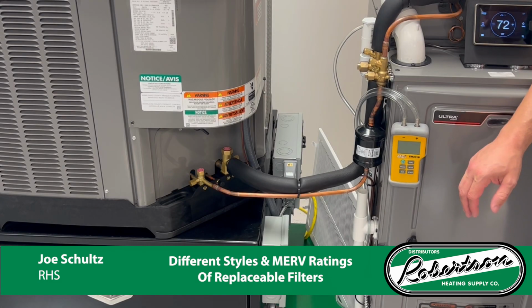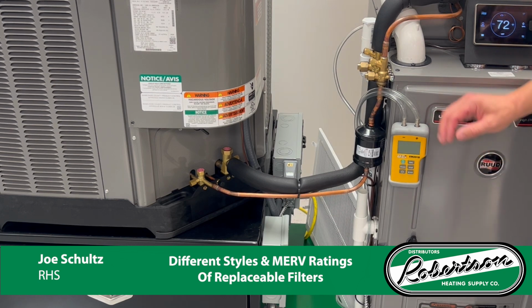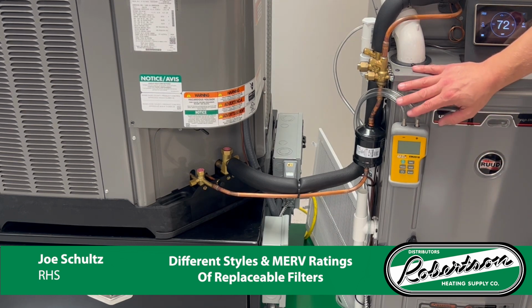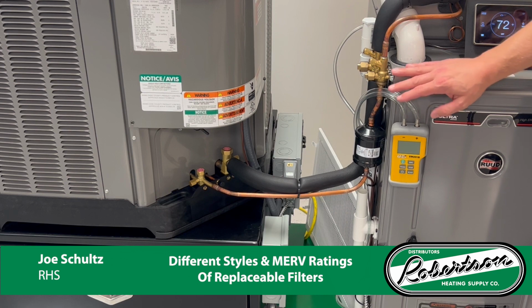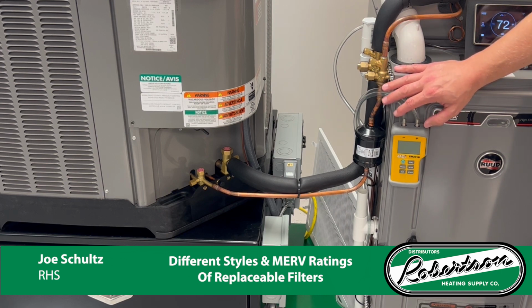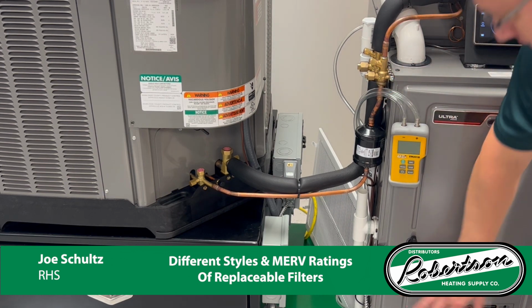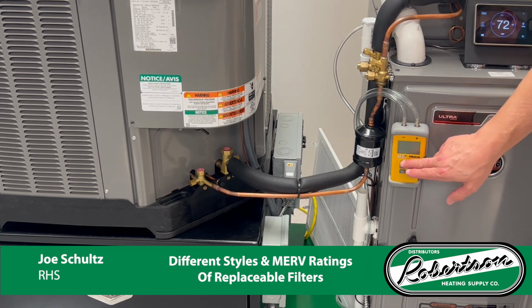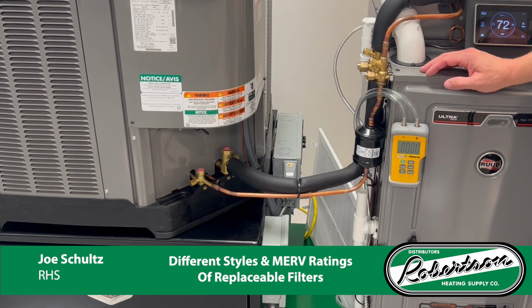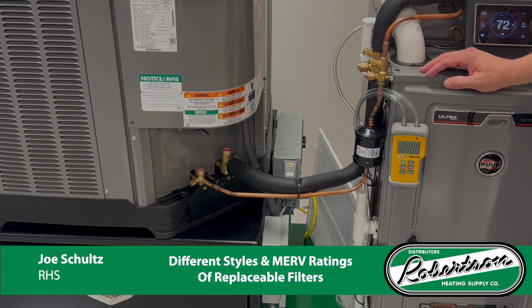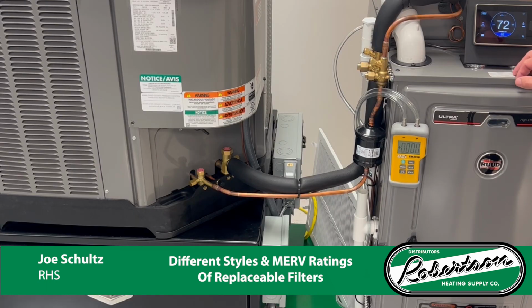So here we got our manometer all set up. So we have our supply positive pressure underneath the coil, and then we have our negative pressure sensor down here in the return cabinet. So we're going to turn on our manometer and make sure it's 0 out before we start the test. Then I'm going to give the unit a call for cooling, and you can see it's all zeroed out.